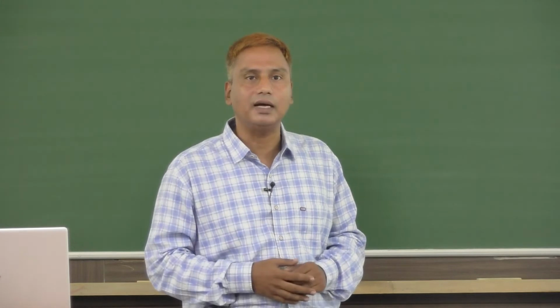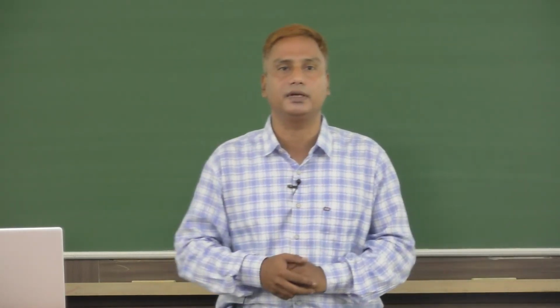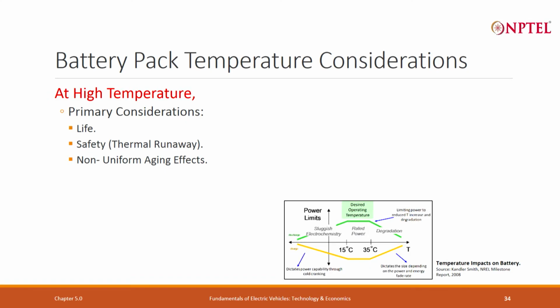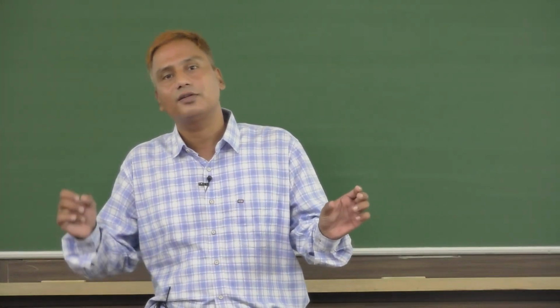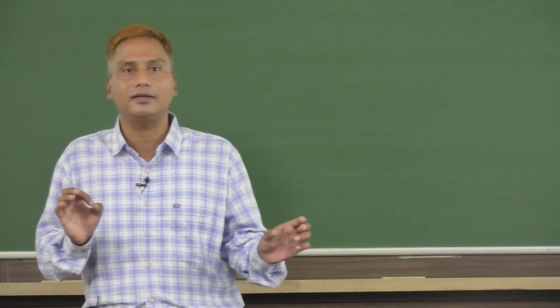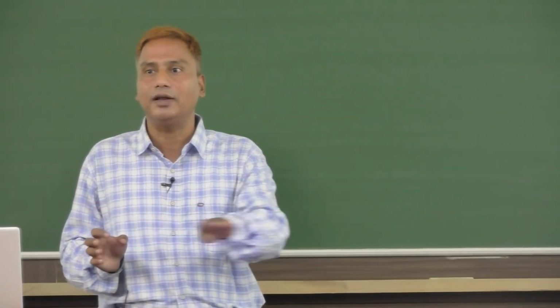It is also a responsibility of thermal design to maintain the same cell temperature across the pack, because non-uniform heating or cooling should be avoided. If one cell is at 35 degrees and another is at 25 degrees, as per theory, the 25 degree cell will have a higher life and degrade less than the 35 degree cell. But in the battery pack, the cell that is most degraded is considered as the life of the whole pack. So if out of 20 cells, one cell has 100 cycles left and another has only 10 cycles left, the pack's life is determined by the cell with only 10 cycles left.